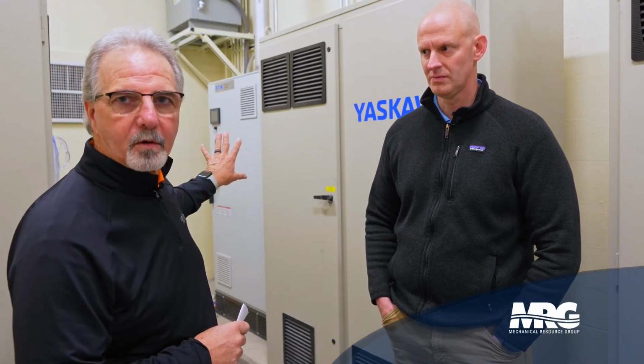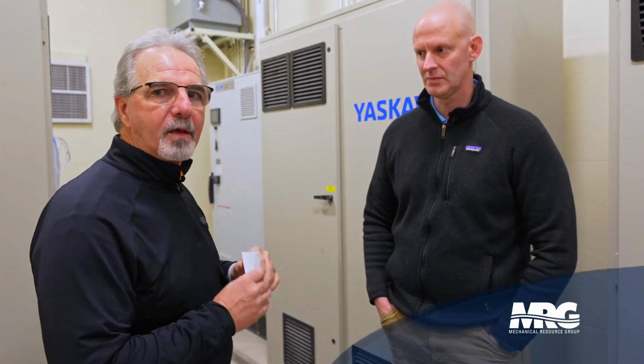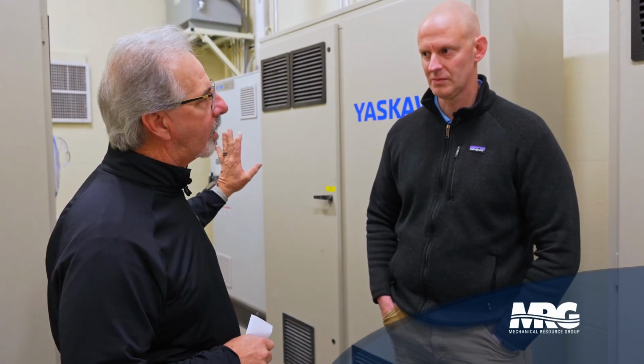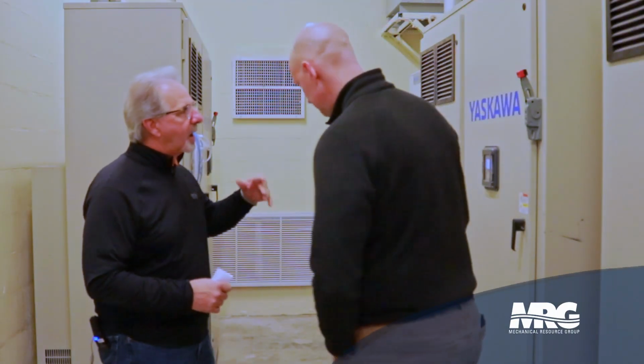All right, we're in the electrical room, and tell me what we got laid out here. It looks like we got some cool stuff. Well, like I was saying, obviously we had a really, really big challenge trying to get all this equipment. We have 1,800 horsepower worth of power that has to come in here. So we had the main switchgear that's over here behind us, but we also had to be able to put 3 of these drives in here. The harmonic filter over here in the corner is the one that really does all the work to attenuate our harmonics. Now, as we go on, I want to explain to you the equipment that we have.